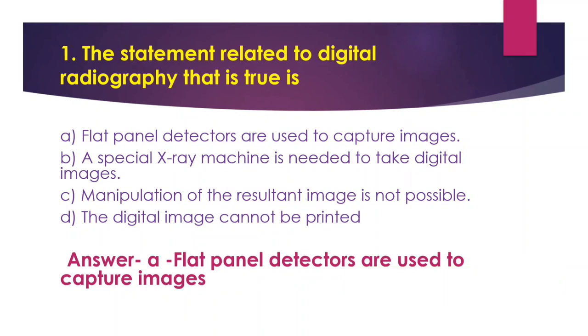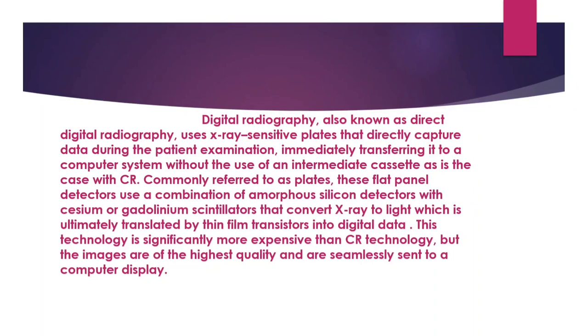The answer is Option A - Flat panel detectors are used to capture images. Digital radiography, also known as direct digital radiography, uses X-ray sensitive plates that directly capture data during patient examination, immediately transferring it to a computer system without the use of an intermediate cassette, as in the case of CR. These flat panel detectors use a combination of amorphous silicon detectors with CsI or gadolinium scintillators that convert X-ray to light.